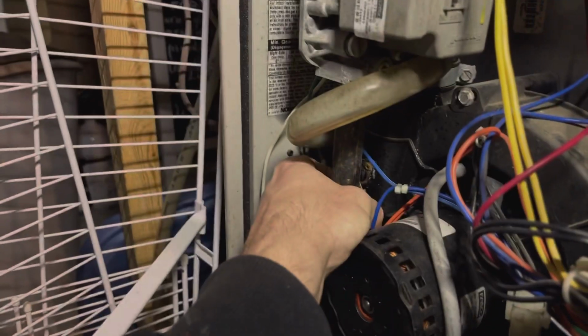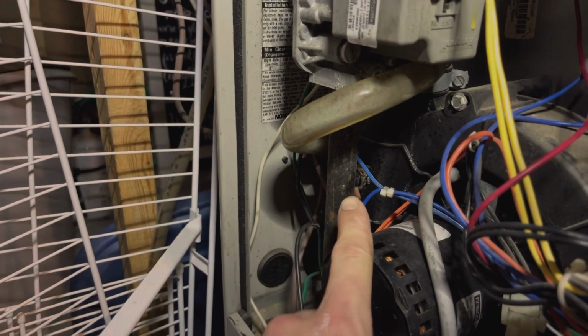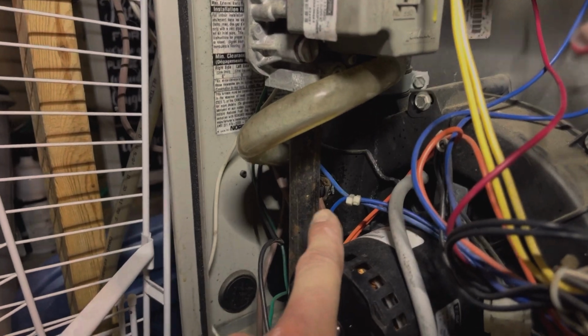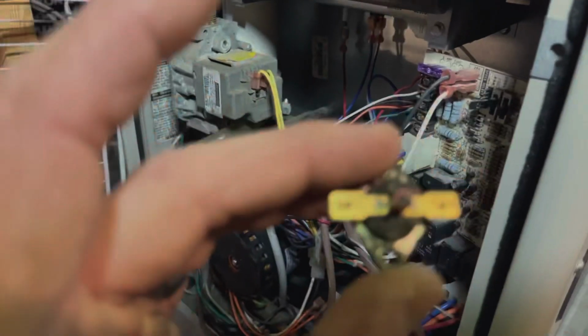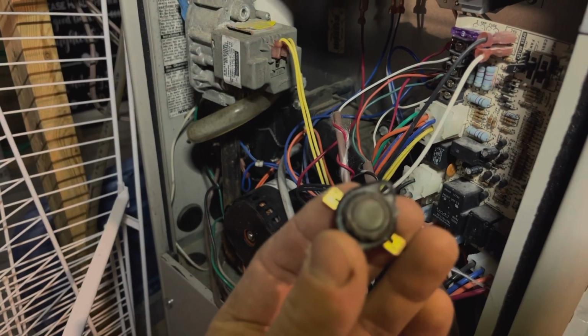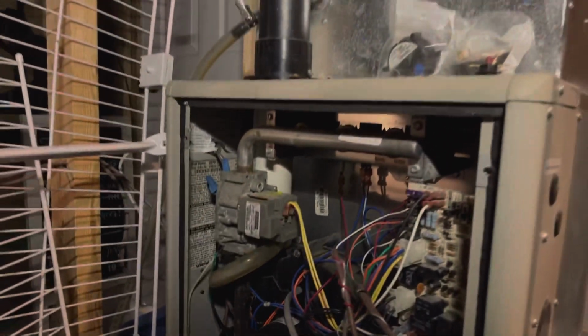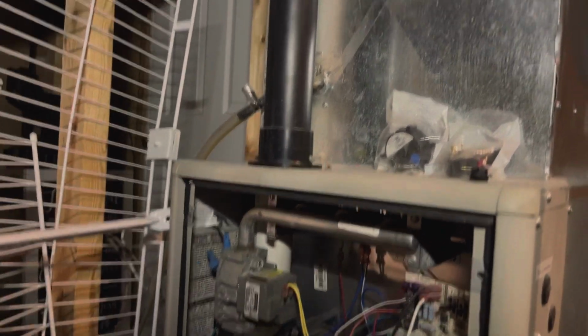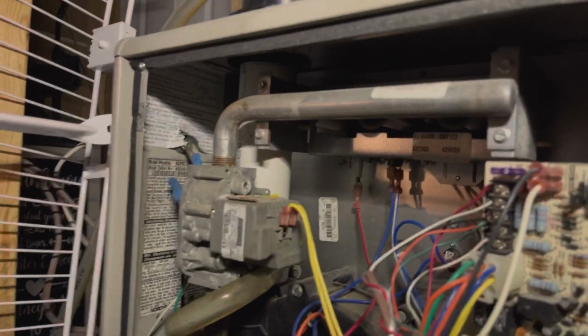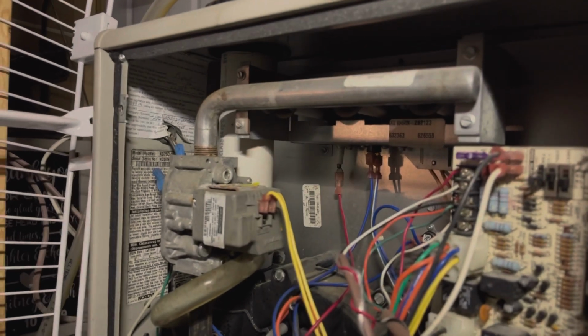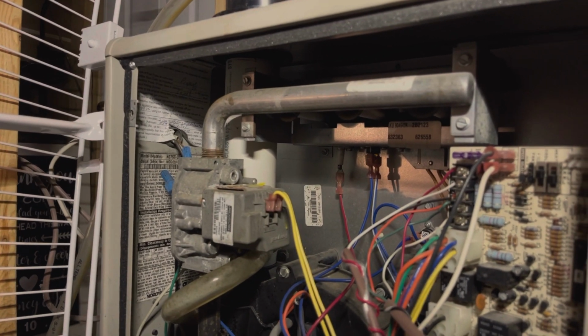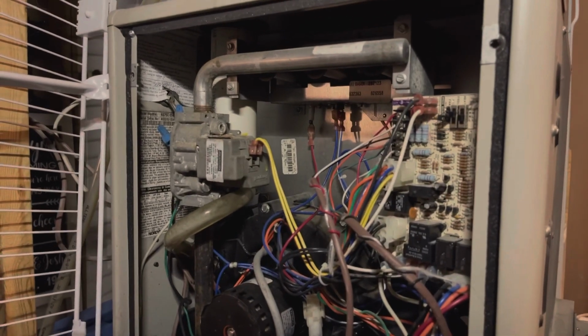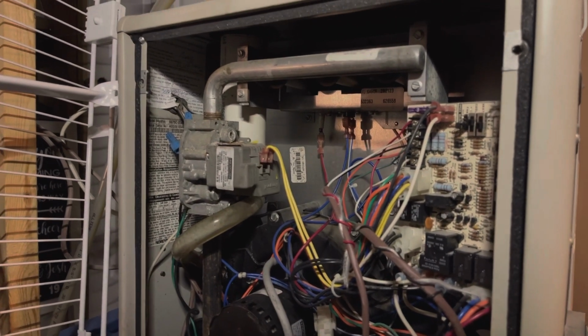Now, my initial thought was that this limit switch was bad when I first was going to work on the furnace. That is because it's gone bad before. It seems to get very corroded, maybe from the outside air coming in, and it causes an issue. With common issues, another issue you could have is this is your air in, and this is your exhaust fan. So those pipes go up and across your basement and outside. So you want to go outside and you want to make sure that they're free and clear of snow and ice buildup, because carbon monoxide can build up in your house because of that. So that can be a danger to you as well as cause a problem to your furnace.